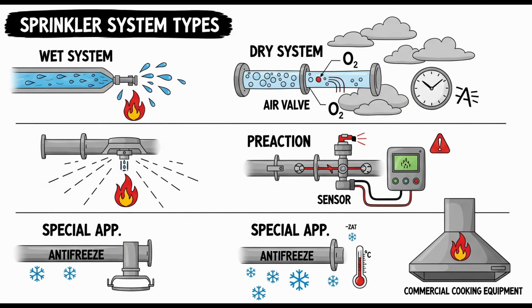Yeah. Apply the knowledge. And considering the incredibly detailed requirements we discussed, maybe for systems operating in constantly refrigerated spaces, or for those protecting high heat cooking equipment, or for systems designed purely for outside exposure protection, why would those specific, often very prescriptive engineering choices we talked about, things like needing specific piping materials or redundant air lines in a freezer, or mandating an automatic fuel shutoff interlock in a kitchen, or requiring a full 60-minute water supply duration for outside sprinklers, why would those precise details be absolutely critical to the overall fire safety strategy and the survival of that particular building you have in mind? Something to think about.